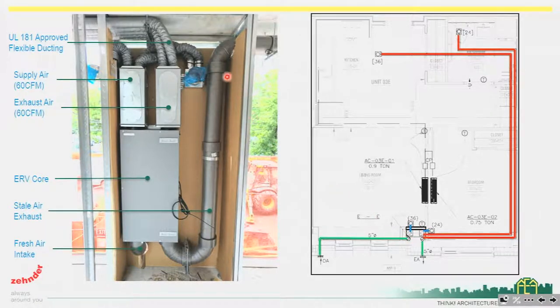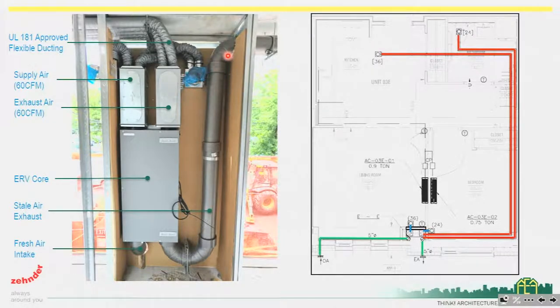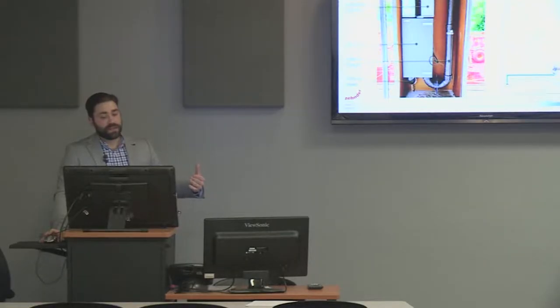The idea is we want to minimize the amount of duct runs to the outdoors, because from an extension-of-the-envelope perspective, these ducts going to the outside — both exhausting stale air and providing fresh air — are extensions of the envelope. They need to perform as well as the envelope itself in order for us to not have heat gain during the summertime or heat loss during the wintertime, since we're going to have very cold or very hot air inside these pipes as they operate continuously.